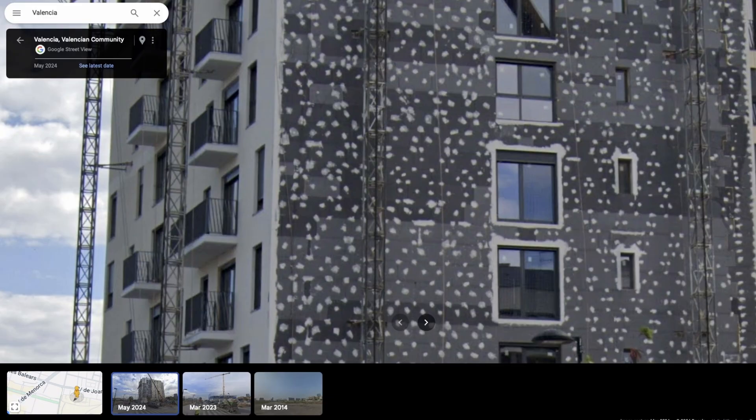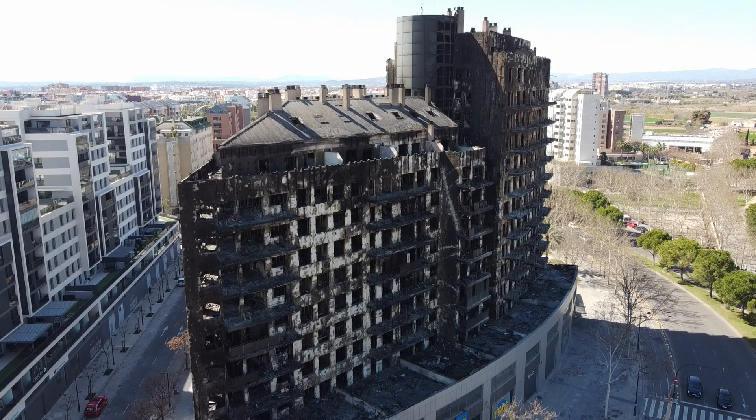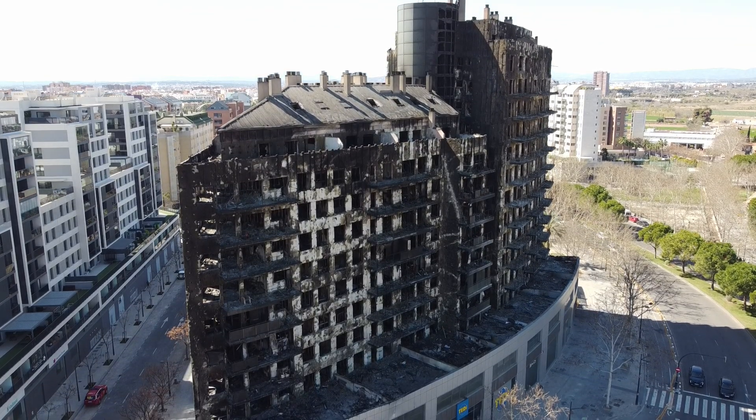In the case of the Valencia building, EPS insulation was installed on the new buildings without any fire barriers. We understand it is a built-to-rent development, so there is likely one client and one facade specialist contractor responsible. Fire safety could be upgraded fairly quickly should residents find the materials used on the facades inappropriate — even if the system was deemed compliant with the current Spanish building code, which it appears to be given the testing process used. And notably, the Campanar building also appears to have been deemed compliant with the Spanish code at the time it was designed — just a thought.